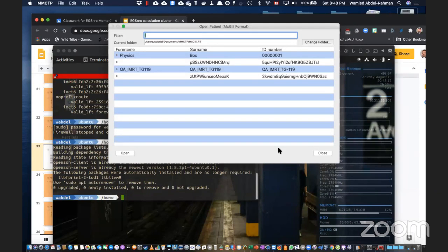Well, during my MSc, we used an ImPACT scan calculator, and we used TLD to look at the dose delivered to the patient. And the machine has a DLP and CTDI to give us an idea of the dose delivered to the patient. And we can now reconfigure that to know what exactly has been delivered to the patient. So one can be able to do a proper dose delivery to the patient, either to reduce the kVp or to reduce the mAs in the subsequent dose to be delivered to the patients.